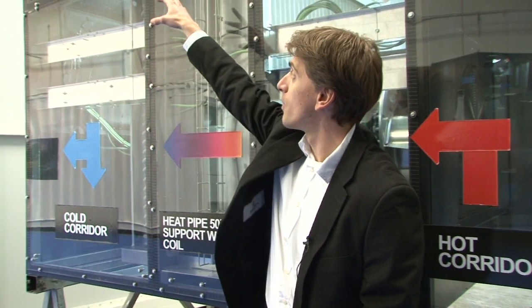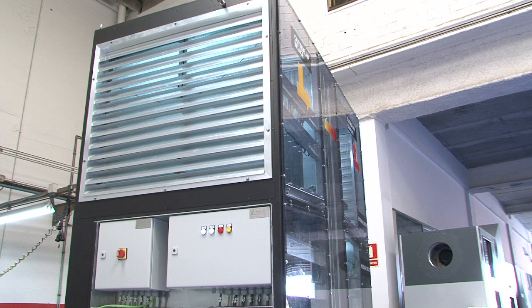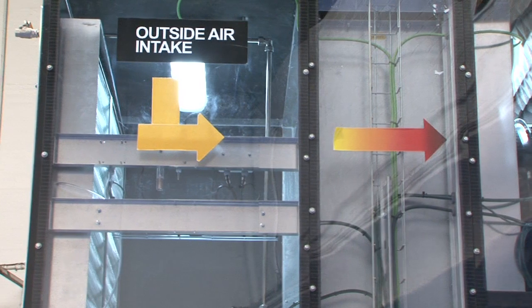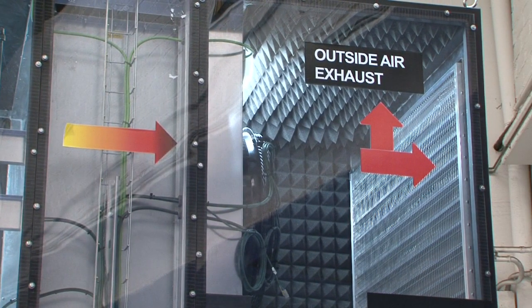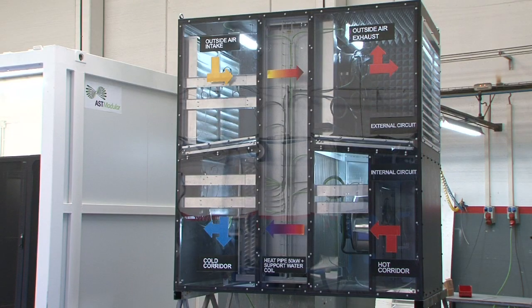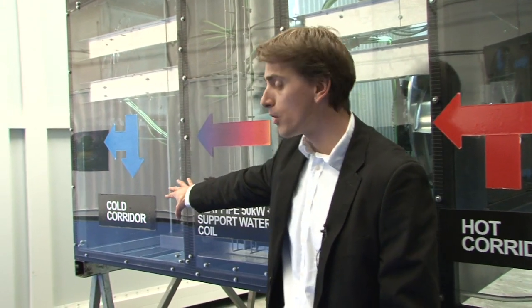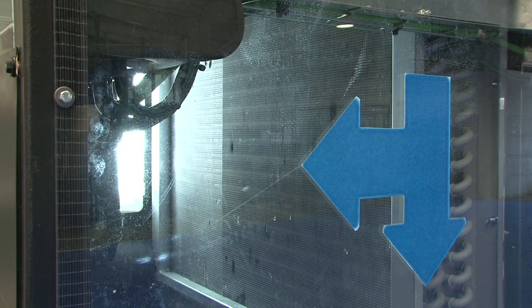If that is not possible during a certain amount of time a year, then we have adiabatic cooling, which is placed on that window over there, which will provide the additional cooling power that is needed to provide those 50 kilowatts of power per module. And then if the external temperature is not sufficient and relative humidity might be too high to use adiabatic, then we have an additional coil here, which can be a chilled water coil or direct expansion evaporator, in order to provide the additional power that the unit needs.